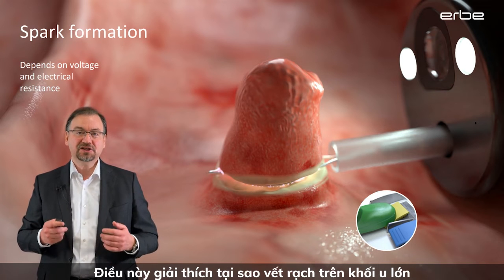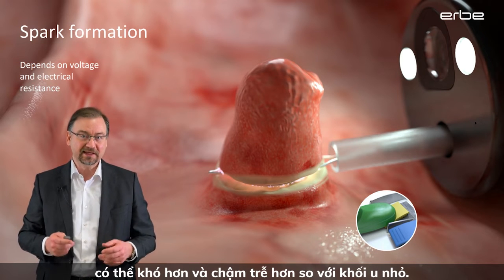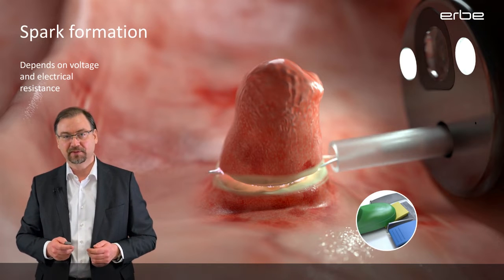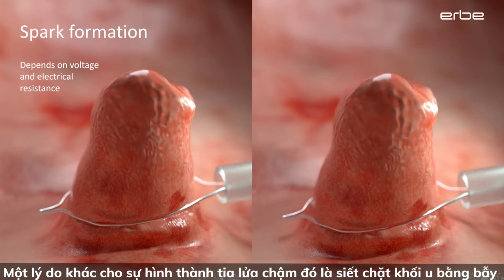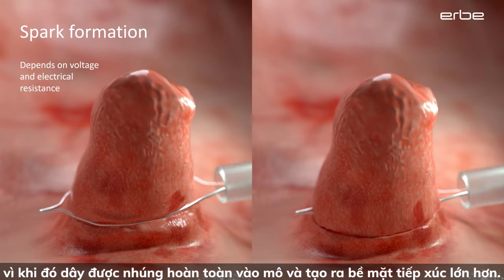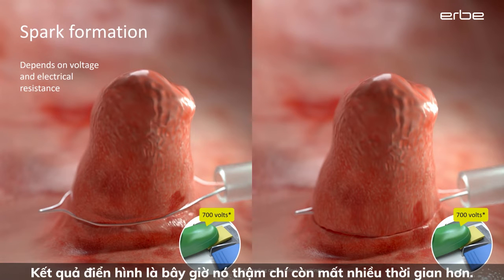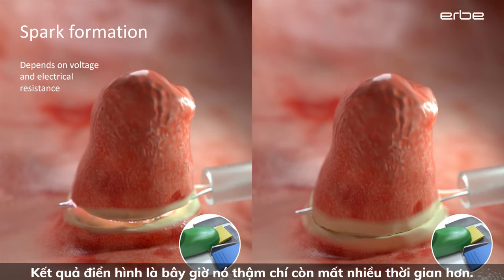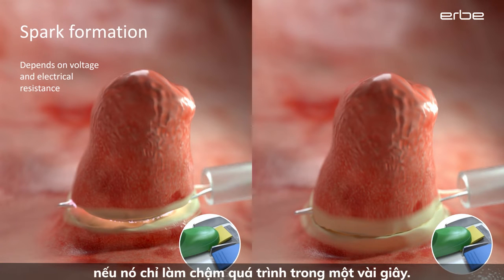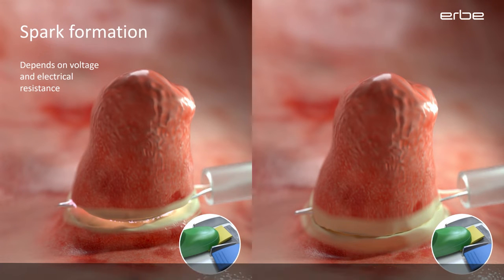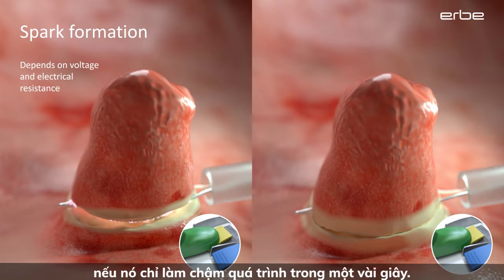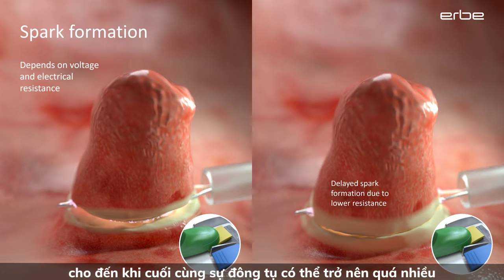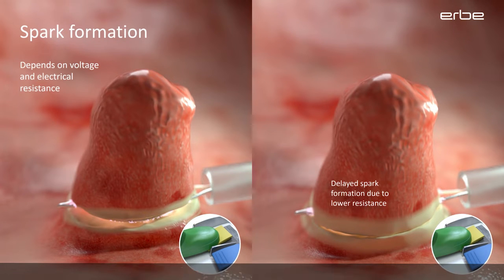This explains why the incision on a larger polyp can be more difficult and delayed in comparison to a smaller polyp. Another reason for a delayed spark formation can be if you squeeze the polyp with a snare, because then the wire is completely embedded in the tissue and the contact surface therefore is even bigger. The typical outcome is that it now takes even longer. It wouldn't be such a big deal if it would just slow down the process for a couple of seconds. The problem is rather that in this situation the current will continuously coagulate and coagulate until eventually the coagulation might become too much before the actual cutting has even begun.